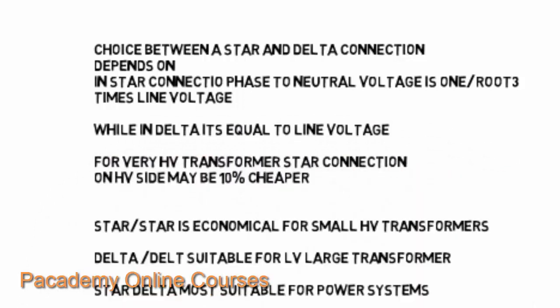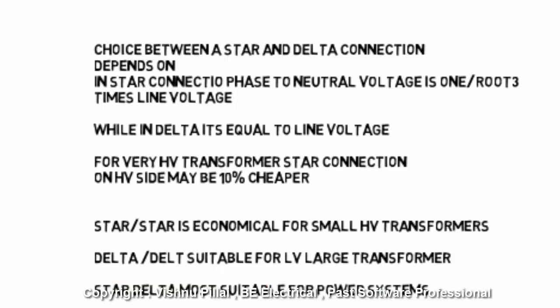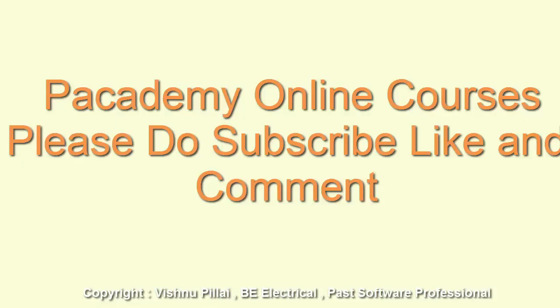The choice between star and delta depends on the application. In a star connection, the phase-to-neutral voltage is 1 over root three times the line voltage, while in delta it equals the line-to-line voltage. For very high-voltage transformers, a star connection on the high-voltage side may be about 10% cheaper, since the line-to-neutral voltage is reduced by root three. Star-star is economical for small high-voltage systems, while delta-delta is suitable for low-voltage large transformers. Star-delta is most suitable for distribution and power systems where a neutral is required, and delta-star is more used where a neutral is needed for power distribution systems.